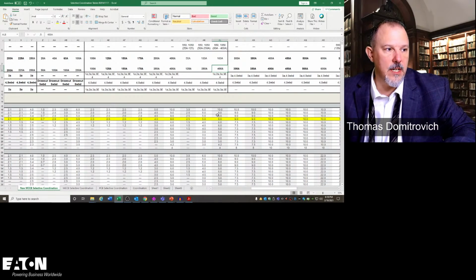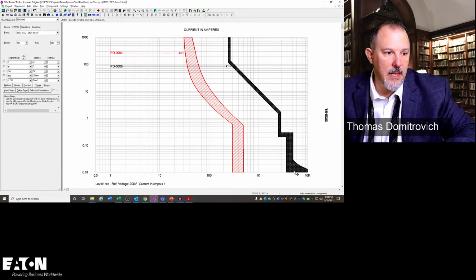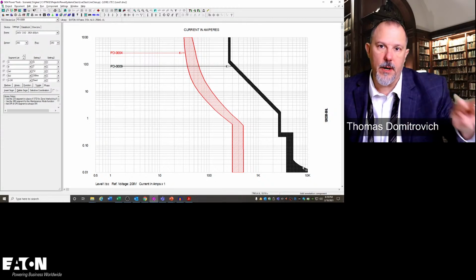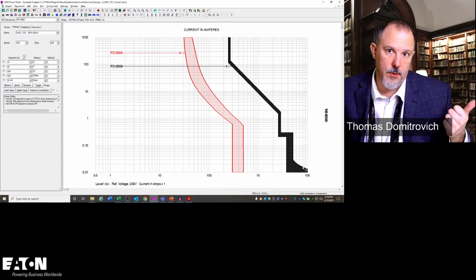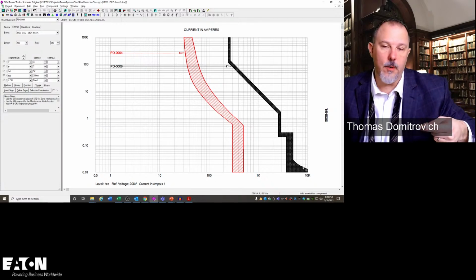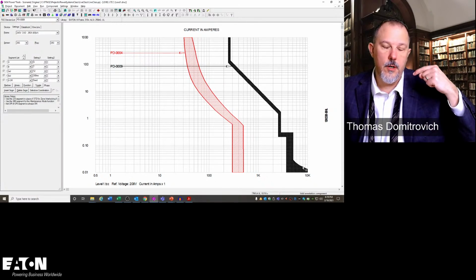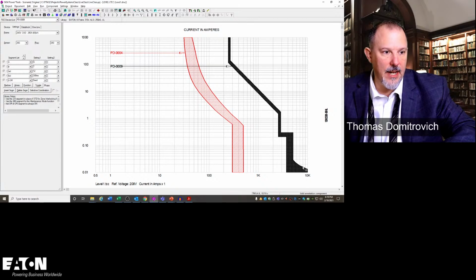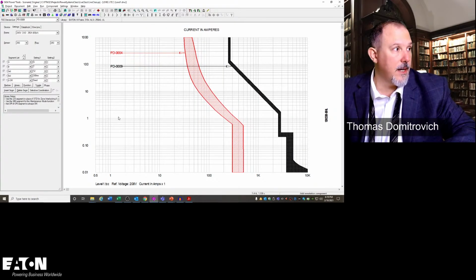Now, the reason I used the tables is because where is 8,000 amps? 8,000 amps is actually right here. Okay, well, I should just look at the tick marks. It's getting late. So this is my 8,000 amp mark right here. I'm in the instantaneous region of both of these breakers, but because of the tables, I know that I selectively coordinate to 8,000 amps. Oh, wait a second. What was my fault current?